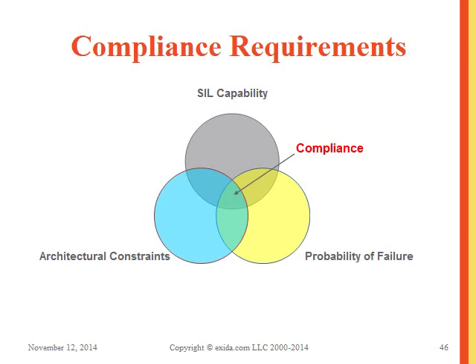Looking at compliance requirements for SIL capability: you need to look at your documentation and all of your processes. You look at the probability of failure and your FMEDA dangerous failure results numbers — that covers the right side. Architectural constraints cover the left side. Only if you meet all three of those are you in actual compliance.